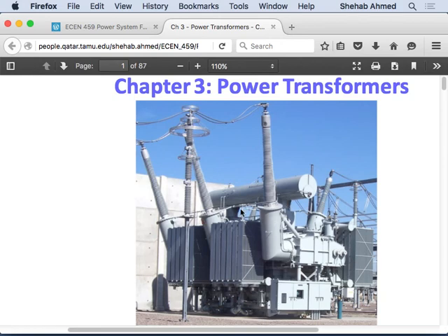They're not clear from the picture here, but they have 3 inputs coming in, and you will have 3 coming out, and these are a little bit longer than these. These are nothing but insulators. This is the high voltage coming in or going out, and this is the low voltage coming in or going out. Of course, if this is shorter than this, it means that the higher voltage is on this side, right?